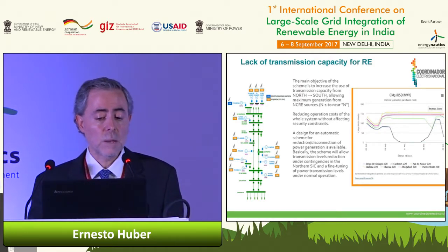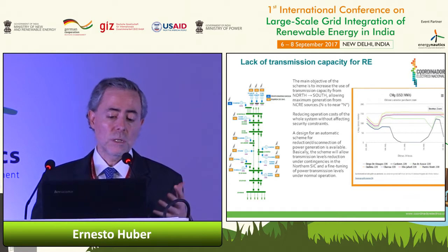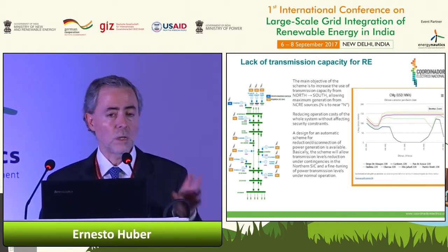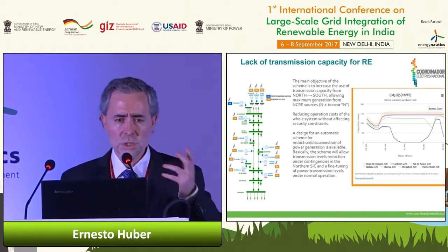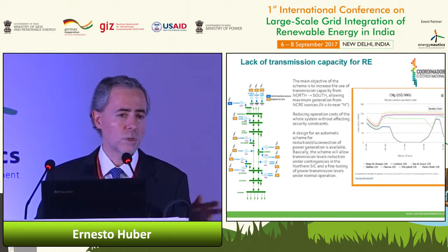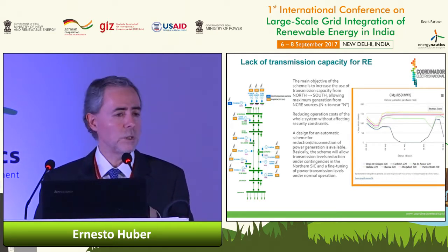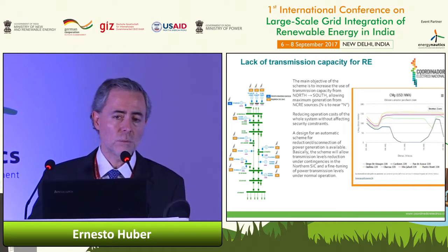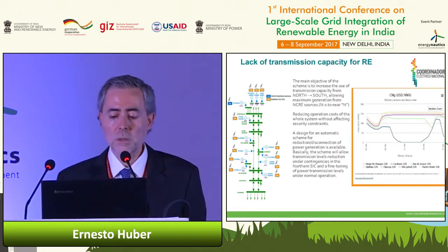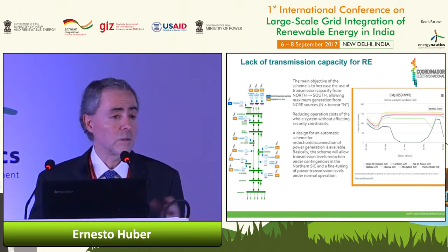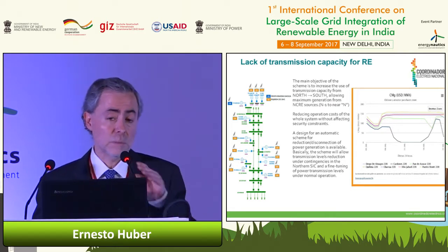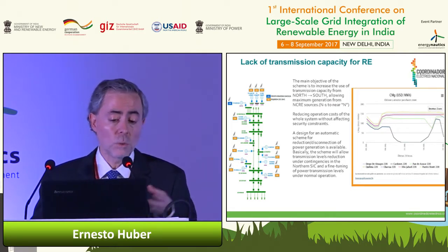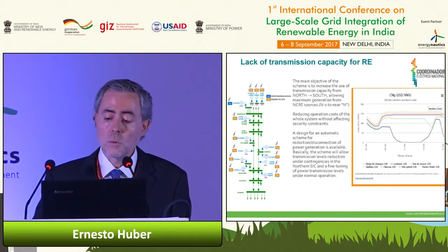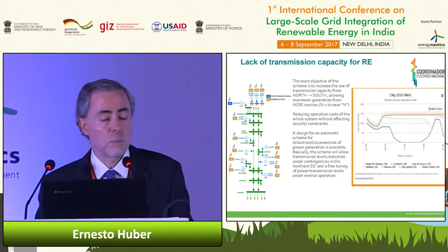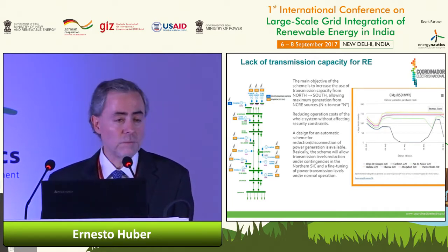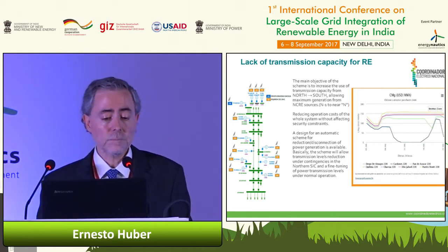We manage the lack of transmission capacity by establishing an automatic scheme to disconnect generation when we lose a circuit, or to fine-tune and adjust the renewable energy generation in that part of the grid. Despite installing this automatic scheme, we still have zero marginal cost in the northern part of this grid.